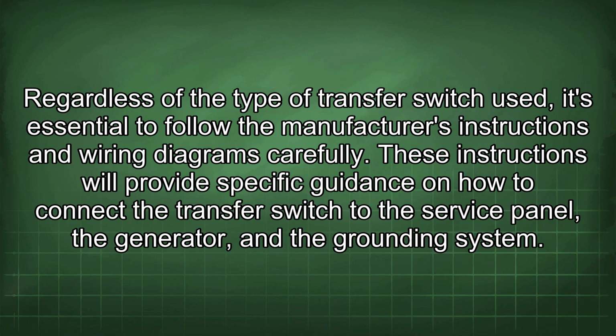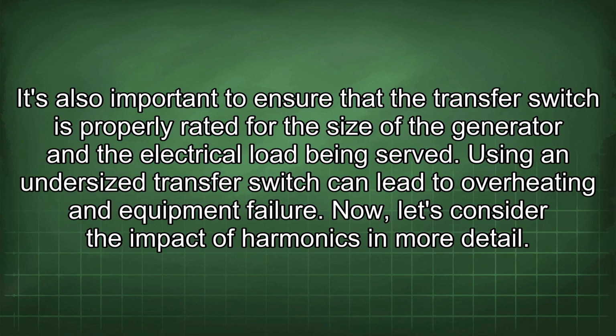Regardless of the type of transfer switch used, it's essential to follow the manufacturer's instructions and wiring diagrams carefully. These instructions will provide specific guidance on how to connect the transfer switch to the service panel, the generator, and the grounding system. It's also important to ensure that the transfer switch is properly rated for the size of the generator and the electrical load being served. Using an undersized transfer switch can lead to overheating and equipment failure.